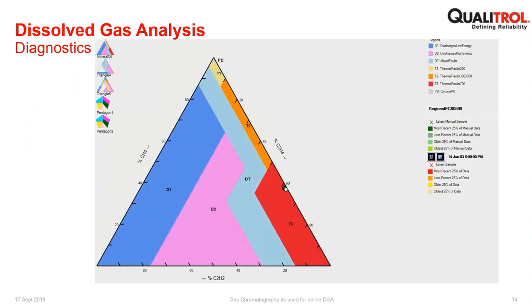This slide is just an illustration of one of the diagnostic techniques. I'm sure most people on the call are familiar. It's Duval triangle. And there are 3 triangles for the application of main tank transformer oil, transformer oil for mineral oil. And there are 2 pentagons developed also by Duval and released in the last number of years. The triangles have been around for well over a decade. The pentagons have been around for a shorter period of time. And basically, they all build upon what's provided in the previous one.